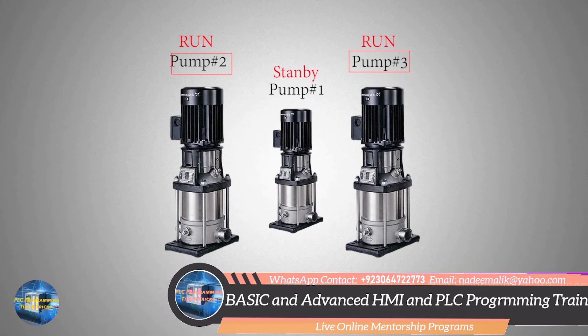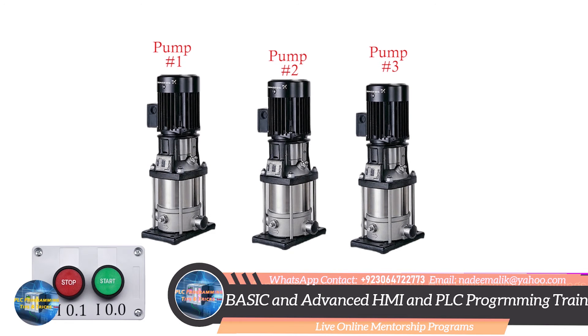This is the duty cycle sequence which we will be making today in the PLC program. Pump number one, two, and three are connected at Q0.0, Q0.1, and Q0.2 outputs of the PLC respectively. Similarly, start and stop push buttons are connected at I0.0 and I0.1 inputs of the PLC.